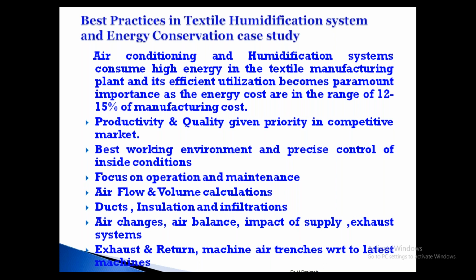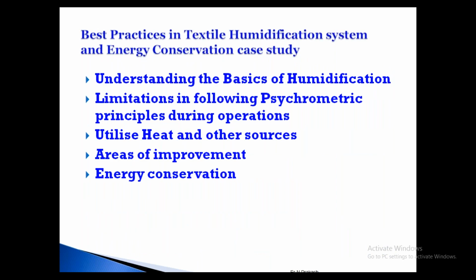So more focus is needed on the operation and maintenance of the humidification plant, its airflow and volume calculations, how the ducts are designed, how the insulation is taken care of, how infiltrations are avoided, how the air changes and air balance work, what is the impact of supply air and exhaust air in the total system, how the trenches are designed, and how it matches with the latest modernization of the machine if it is a retrofit project. All these things are important to know about the energy aspects as well as the textile humidification system.